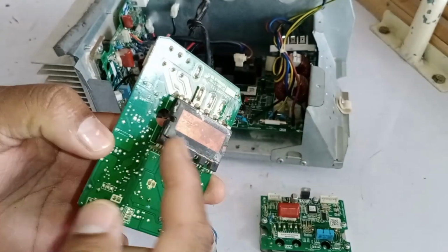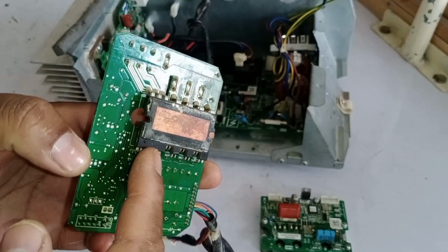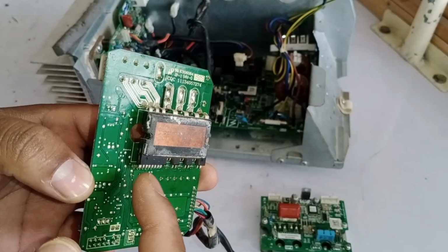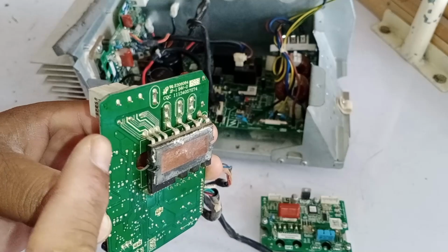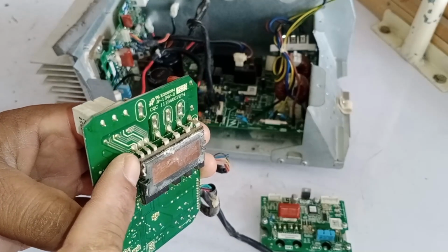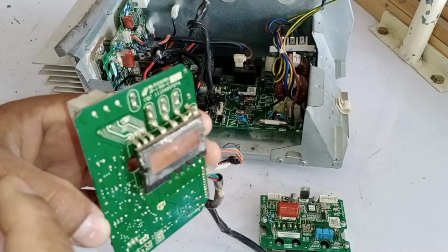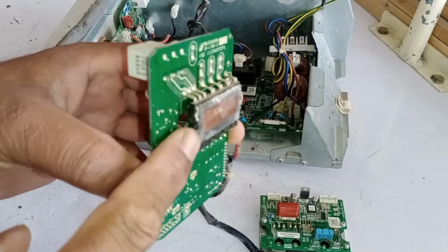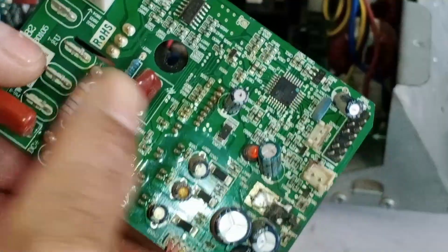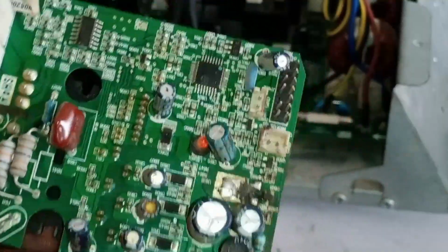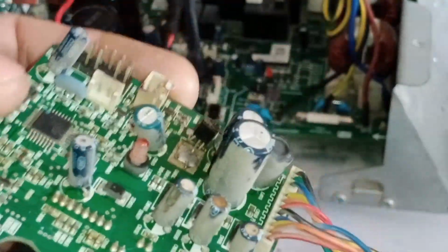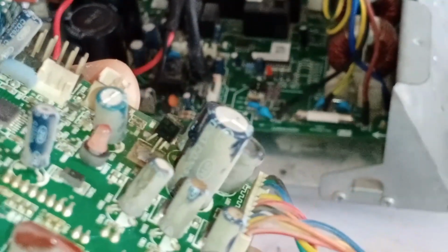Generally, the possibility of the IPM PCB being faulty is low because the issue is related to communication, but there is still a chance that it could have a short circuit. This type of short circuit is often not visible, and you may only detect it using a multimeter, but the chance of this being the issue is low. The IPM PCB works on 3.3 volts, and its microcontroller also operates at 3.3 volts. To achieve this, a 3.3 volt voltage regulator is used on the PCB.